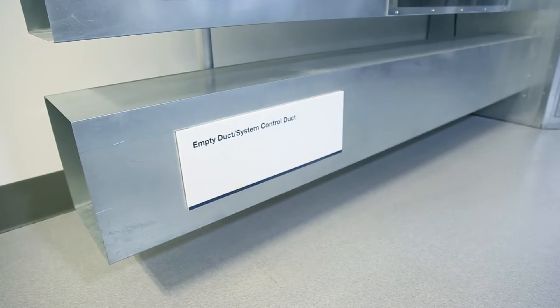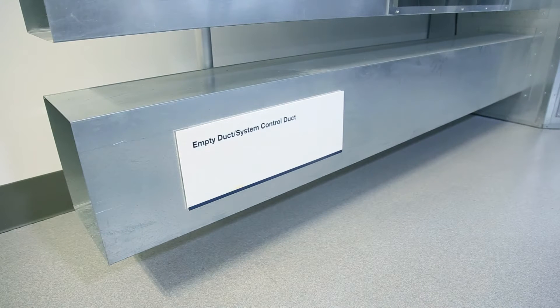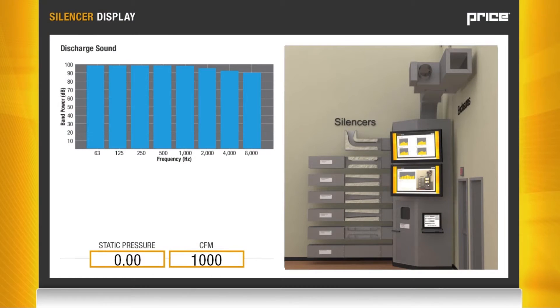We will start with measuring the sound source through the empty duct. This will give us our base sound level for all of the tests and there's a microphone at the end of the duct capturing the sound measurement. You can see on the graph that the sound source is relatively constant in all octave bands for the empty duct sound measurement. The pressure drop is also measured at 0 inches of static pressure as there is nothing in the airstream.